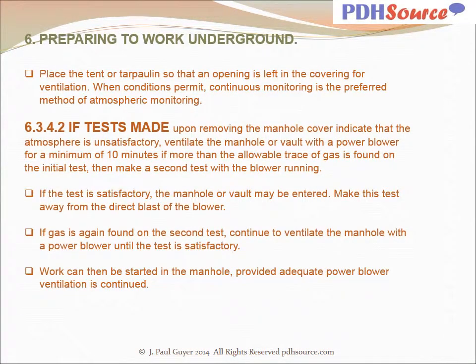Place the tent or tarpaulin so that an opening is left in the covering for ventilation. When conditions permit, continuous monitoring is the preferred method of atmospheric monitoring. If tests made upon removing the manhole cover indicate that the atmosphere is unsatisfactory, ventilate the manhole or vault with a power blower for a minimum of 10 minutes if more than the allowable trace of gas is found on the initial test. Then make a second test with the blower running. If the test is satisfactory, the manhole or vault may be entered.